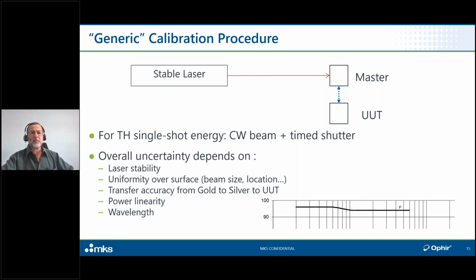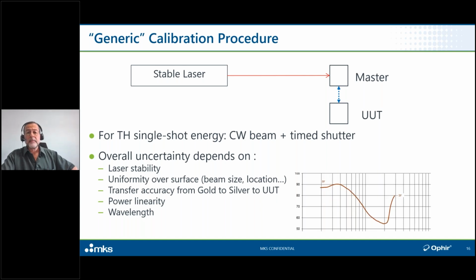Wavelength: we have some sensors whose absorber has a very flat spectral response, and it might be enough to calibrate at one wavelength here, one wavelength there, and then over the whole spectral range, we are confident that the accuracy will be within the numbers that we specify. We have other sensors, though, whose spectral response is very not flat, and here it won't be enough to calibrate at 2 or 3 or 5 points. We have to calibrate using a full spectral curve with a computer-controlled monochromator, and then we need to anchor that whole curve at a certain number of very specifically chosen laser wavelengths, and so on.